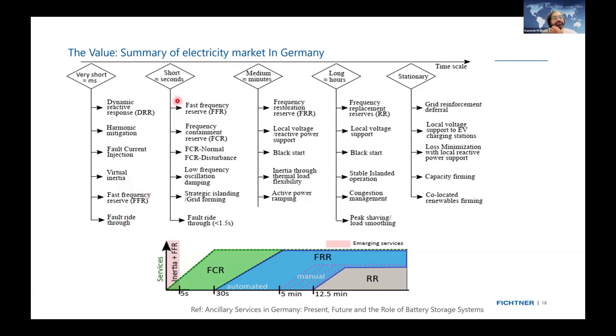In terms of seconds, we have fast frequency response, and then islanding or grid forming. Typically everywhere right now is grid following. This is grid forming, such as if there's a total blackout, I want to do a black start. So my PCS, the bidirectional converter, will act as a grid and form a grid. It's again a challenging research topic among peers.